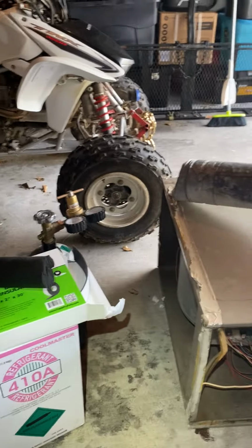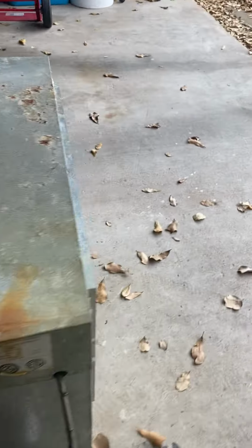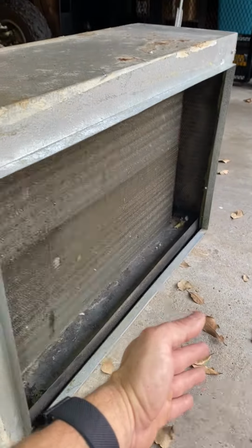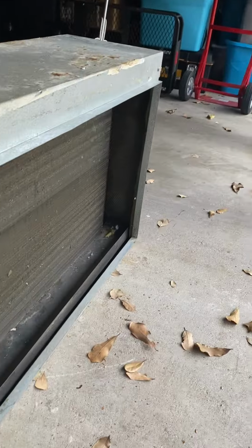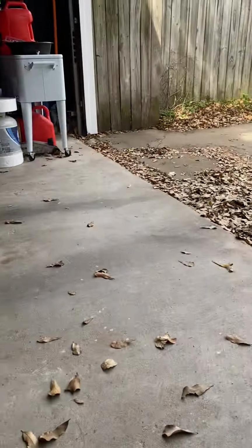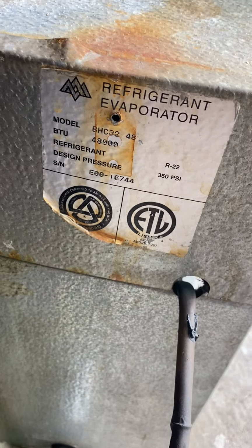Typically, one of the things they do is they test the air coming in the return, and then they retest the air coming out of the coil. This is where your plenum or your ductwork should be, and that's called your delta T. It should be between 18 and 21 degrees, depending. Called your delta T. This unit is an R22, an old unit. That Freon isn't being used anymore.